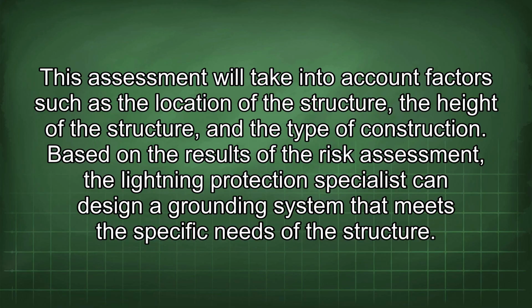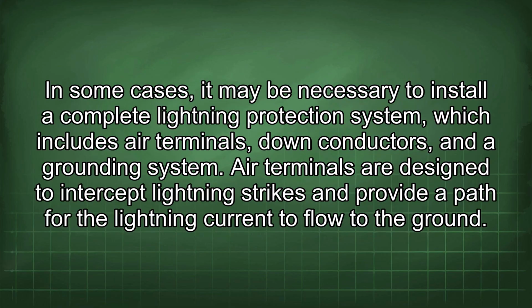Based on the results of the risk assessment, the lightning protection specialist can design a grounding system that meets the specific needs of the structure. In some cases, it may be necessary to install a complete lightning protection system, which includes air terminals, down conductors, and a grounding system. Air terminals are designed to intercept lightning strikes and provide a path for the lightning current to flow to the ground.